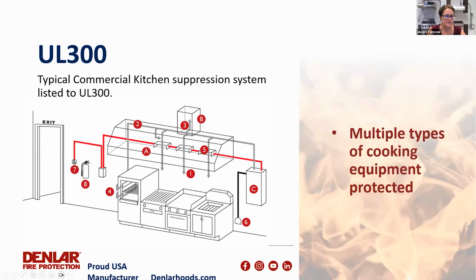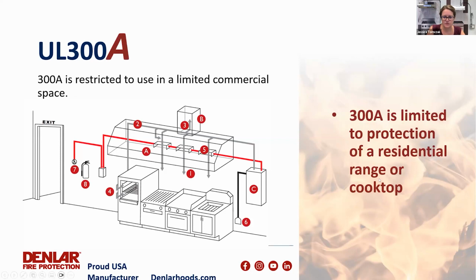This is what you're going to see. You go out to eat in a restaurant kitchen or in a cafeteria, if you're in a hospital or dormitory, even in a college kitchen. So what you'll see is there's a pre-pipe system, there's multiple discharge nozzles, and there are multiple cooking appliances being protected here. You can see there's a grill, a griddle, a deep fryer, there's a pull station, there's going to be a fuel disconnect. It's going to have a wet chemical system. And when you look at a UL 300A system, we can basically look at it as a subcategory of that. So what we are doing is 300A is specific to being used in a limited commercial space to protect a residential range or cooktop. So that is maintaining the same things.